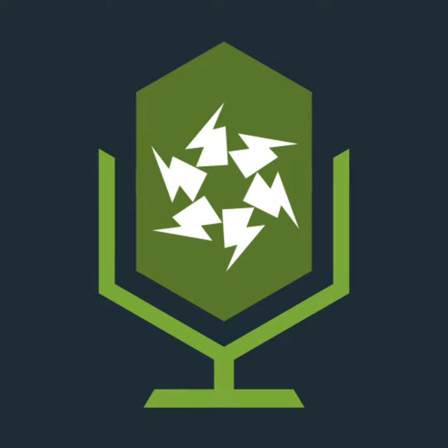Adding a demand, increasing IB, increases volt drop. Any of these things could make the system less safe if it was already not compliant. And we would sometimes have to improve measures to make it compliant for us to do our work. So that's what they're saying. We need to verify that the ADS and all the other protective measures we choose to use are going to be safe for our additions and alterations.